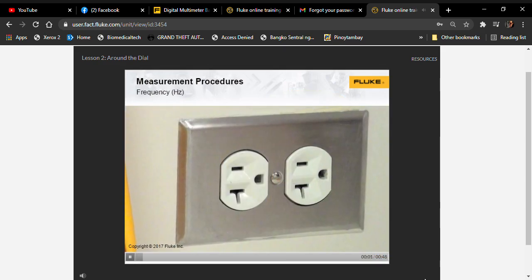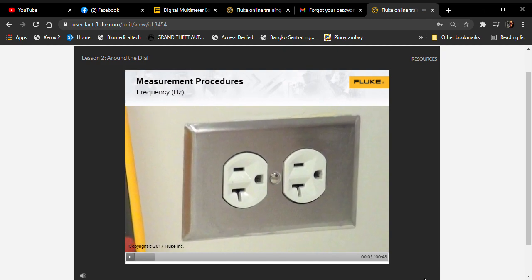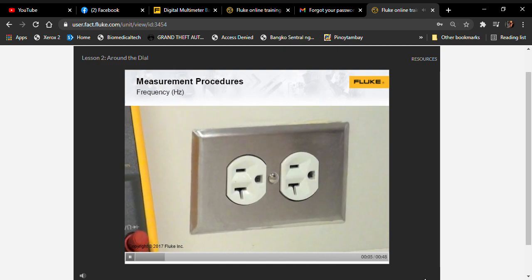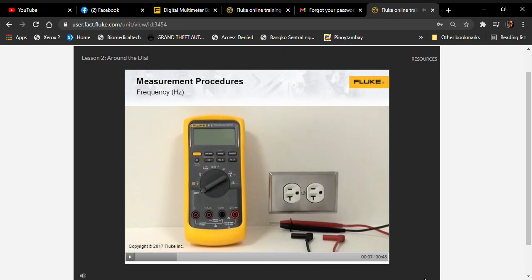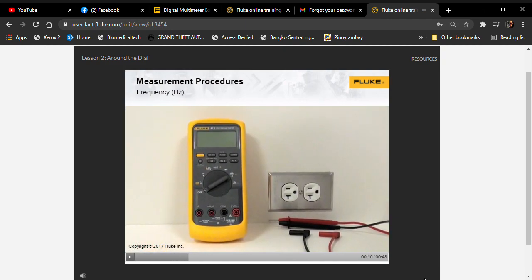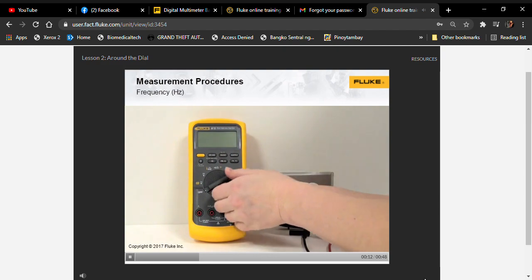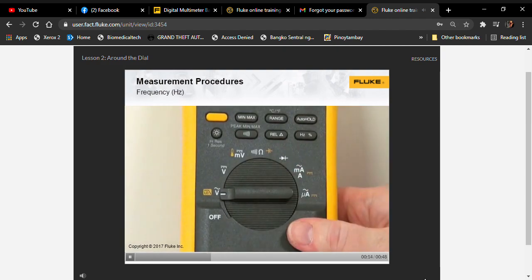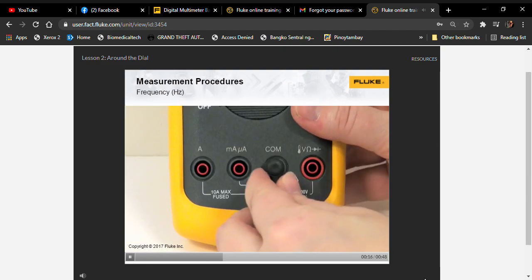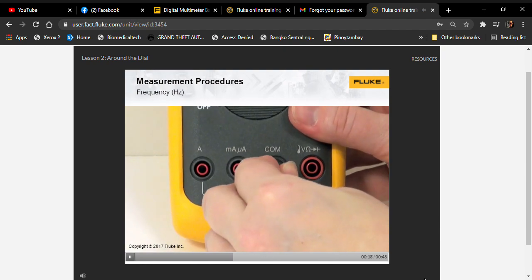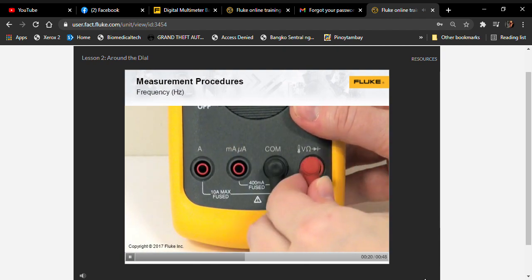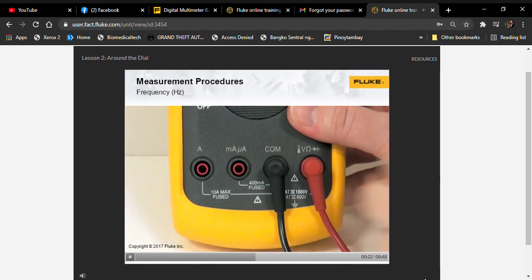The procedure for measuring AC frequency begins in the same way as measuring AC voltage. To set up this multimeter to measure AC frequency, the selector switch is moved to the AC voltage position. The test leads are then plugged into the multimeter's input jacks, the black lead into the common jack and the red lead into the red input jack indicated for voltage.